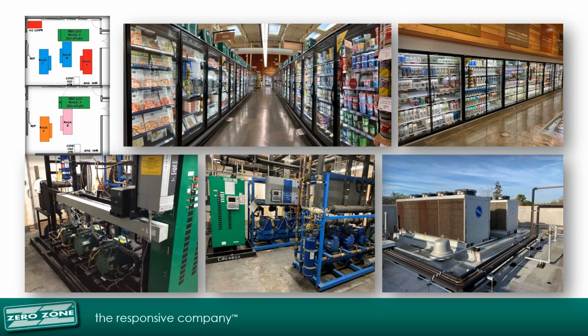Here are some photos of the finished outcome. New low temperature CO2 rack with low temperature door cases, reduced medium temperature load by adding doors to the medium temp fixtures, installed new BAC Trillium condensers for the medium temperature racks. Overall, a system upgrade that allowed Whole Foods to significantly reduce their weighted average GWP.